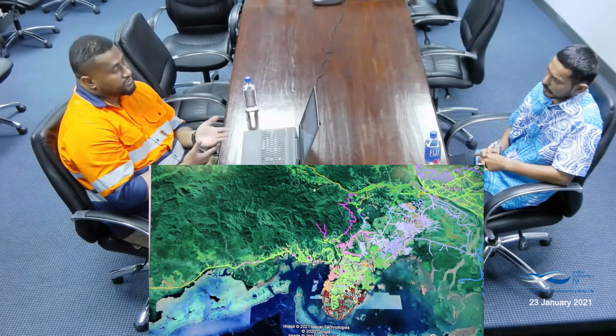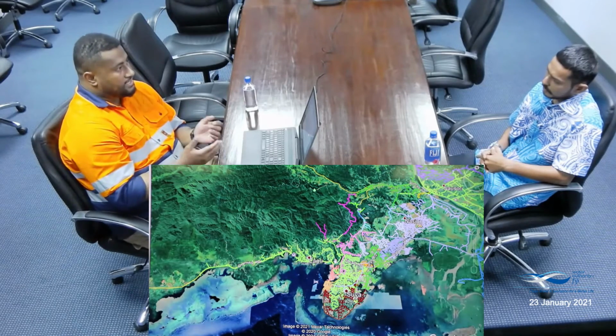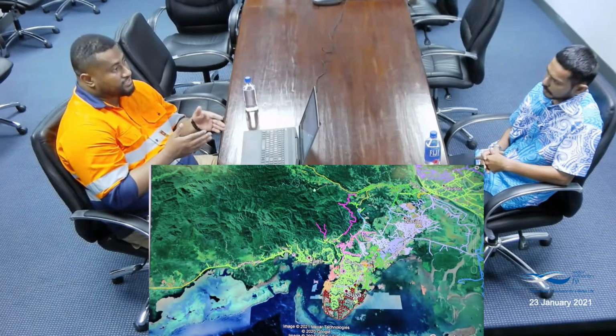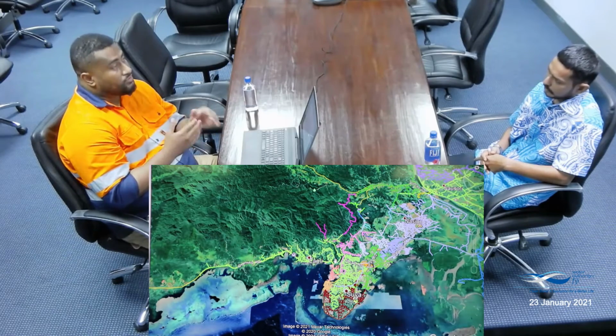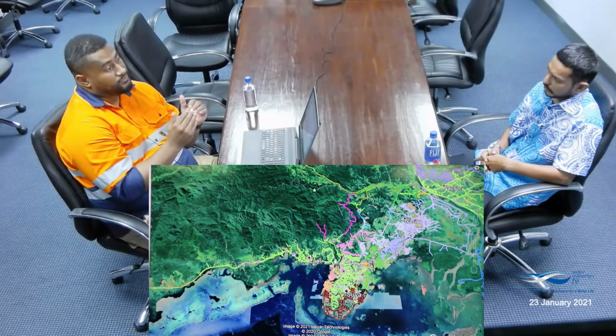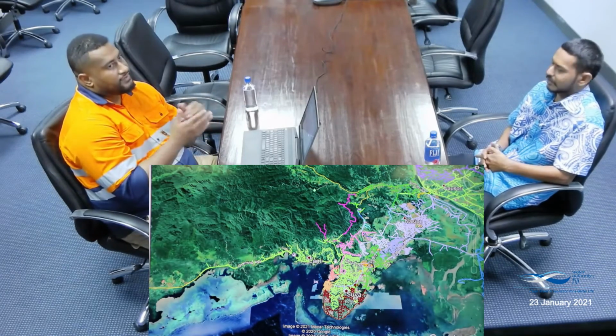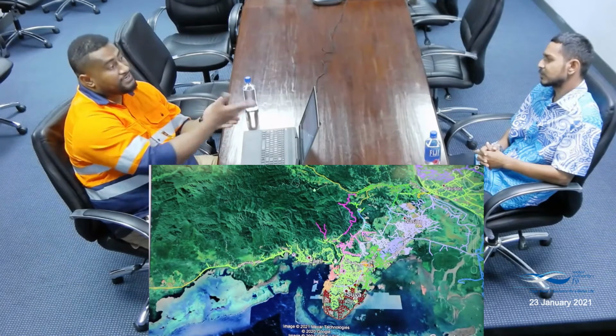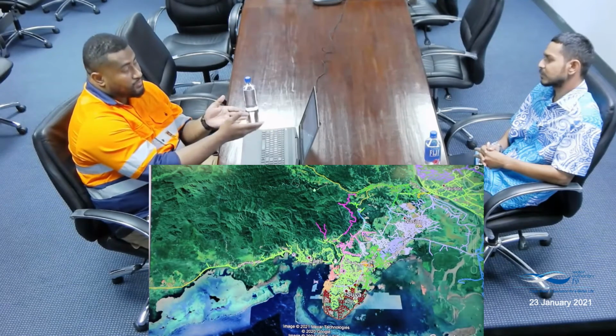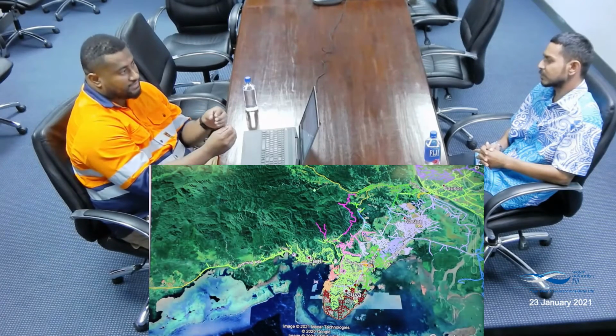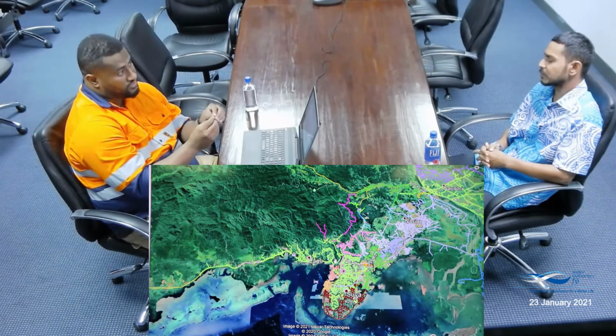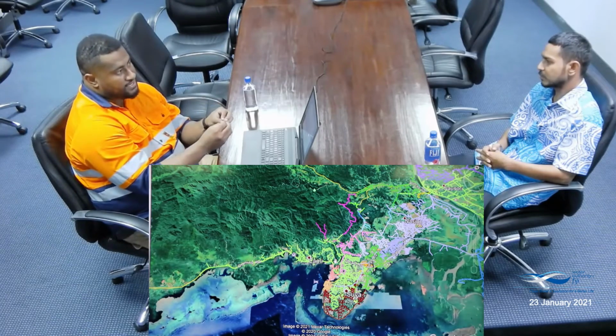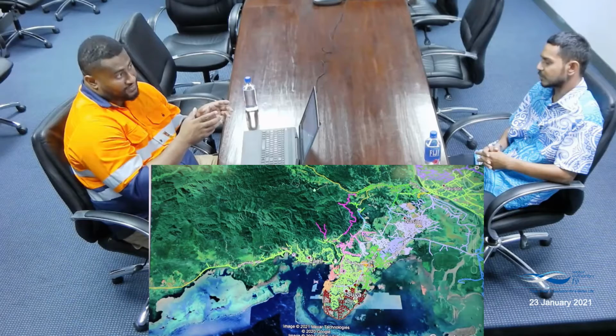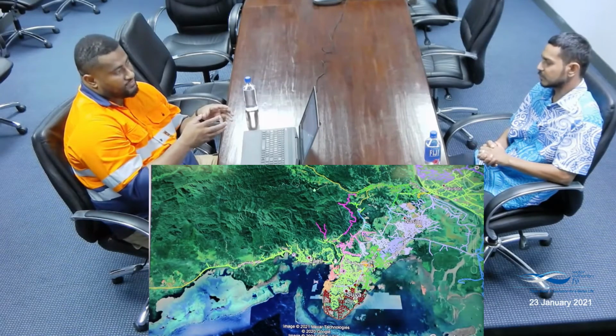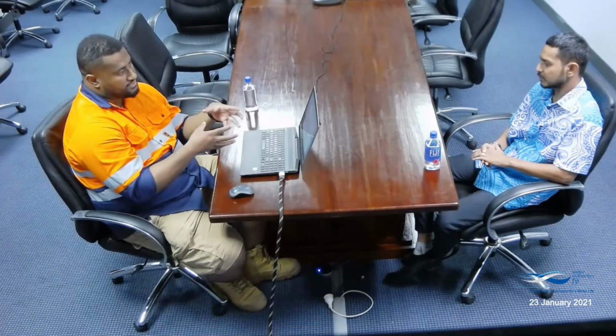Once we introduce the 20 million liter water treatment plant, that gives us the opportunity to increase production, or more or less maintain our production levels as a backup. Right now we push 70 million liters into the water treatment plant, but when it rains we can only push in 60, sometimes 55 million liters, because of the quality of the raw water. If we put in that additional water treatment plant, we can maintain pushing in the 75 million liters, because we'll now have the treatment capacity within the plant to cover that.